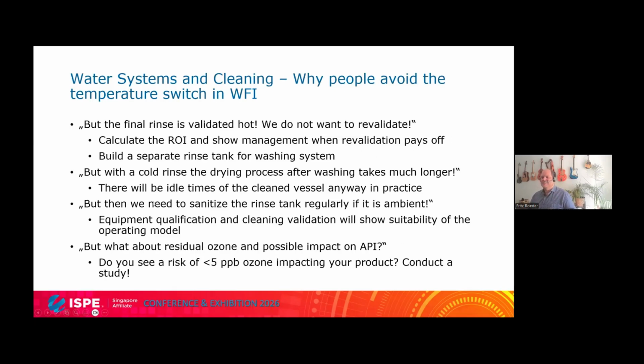Next one: but then we need to sanitize the rinse tank regularly. If they have a rinse tank in the SIP unit and the water is not hot, then they need to sanitize. But their qualification and cleaning validation will show the suitability of the model. It could happen that you need to sanitize it, but if you have an ozonated cold loop, you could also fill the tank sometimes with ozonated water. It's no problem, it's also possible.